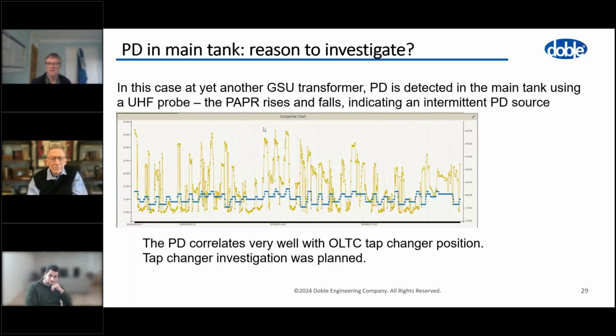The interesting thing was the day that they had the outage to take this out and investigate, drain the oil, they were halfway through draining the oil when grid control rang up and said, can you put this back in service? We need you online to support the grid.